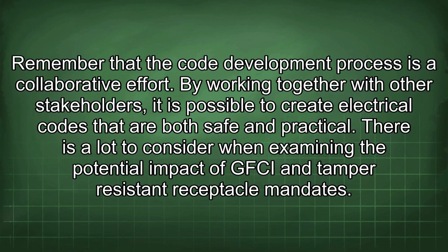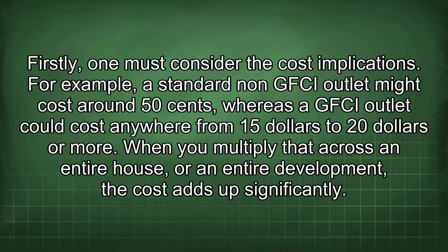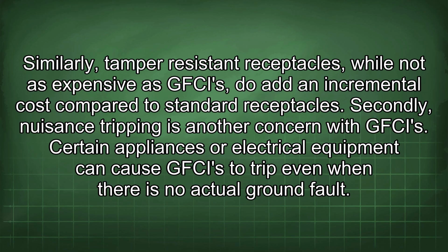There is a lot to consider when examining the potential impact of GFCI and tamper-resistant receptacle mandates. Firstly, one must consider the cost implications. For example, a standard non-GFCI outlet might cost around 50 cents, whereas a GFCI outlet could cost anywhere from $15 to $20 or more. When you multiply that across an entire house or an entire development, the cost adds up significantly. Similarly, tamper-resistant receptacles, while not as expensive as GFCIs, do add an incremental cost compared to standard receptacles.